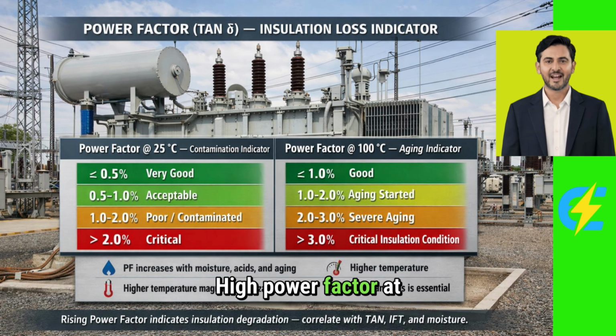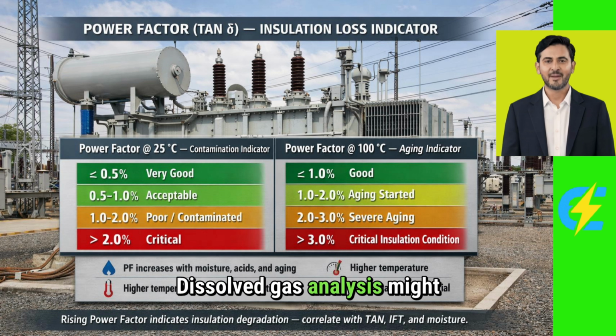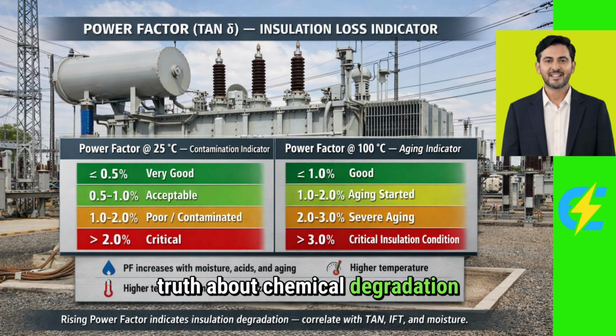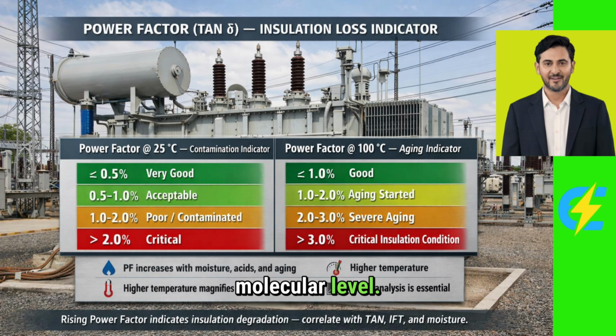High power factor at 100 degrees Celsius is a serious aging signal that many other tests miss. You see, breakdown voltage can remain acceptable even when the oil is chemically deteriorating. Dissolved gas analysis might not show immediate problems, but power factor at 100 degrees reveals the truth about chemical degradation that's happening at the molecular level.